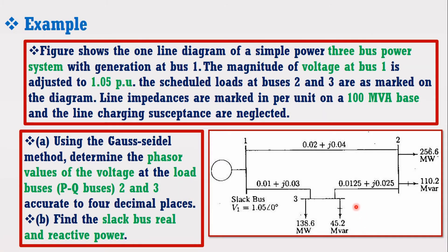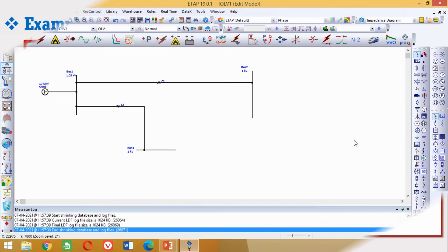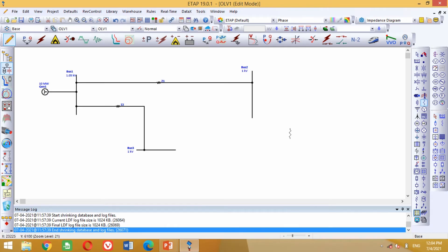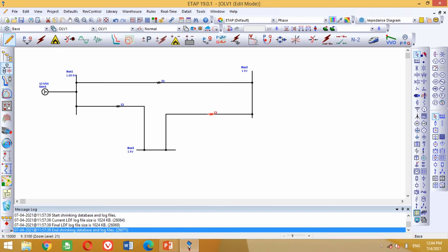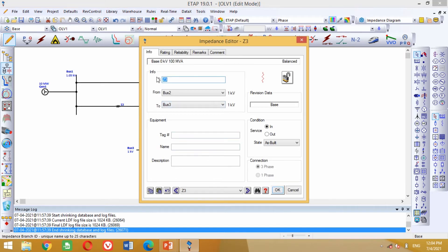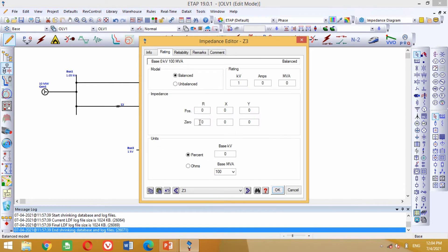Look at the figure again. The transmission line from bus 2 to bus 3 has resistance of 0.0125 and reactance of 0.025 per unit. Come to the model again. Bring this impedance block from here in the model and paste it here. Rotate it by pressing Ctrl+R and connect it between bus 2 and bus 3. Now double click on this block to insert the transmission line data. In the rating section, put 1.25 in the resistance value and 2.5 in the reactance value. Write 1 here in the base kV and press OK.